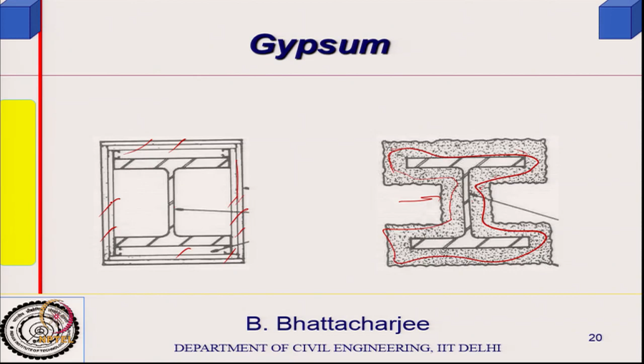So gypsum spray or gypsum board is used around steel in order to protect steel. You will find gyp board false ceilings all over the place. One of the reasons is that it will not spread fire. They are very good against fire. Steel can also be encased in concrete. Exposed steel is rarely used. I will either encase it in gypsum board, spray gypsum, or encase it in concrete, because concrete is a good insulator. Now the thermal conductivity of steel, we shall see it again later on, is 50 watt.